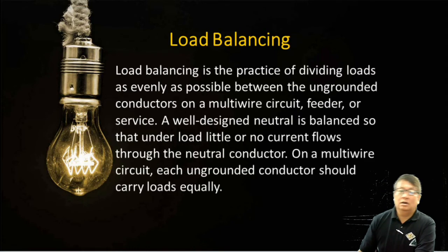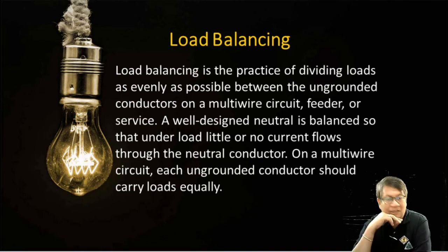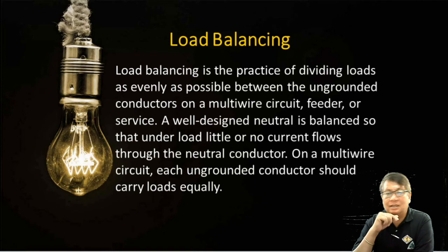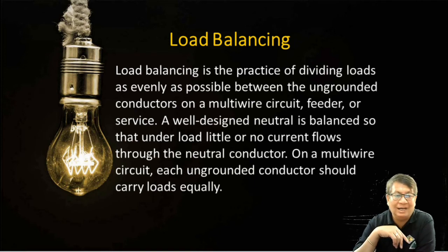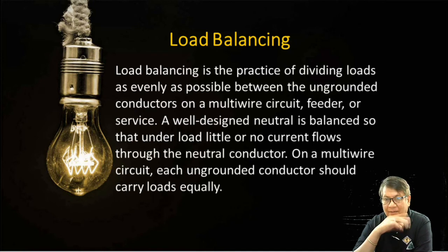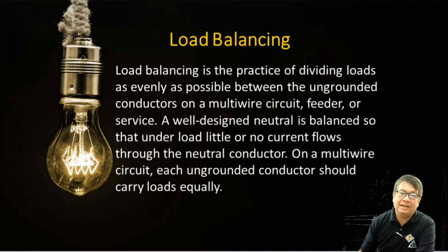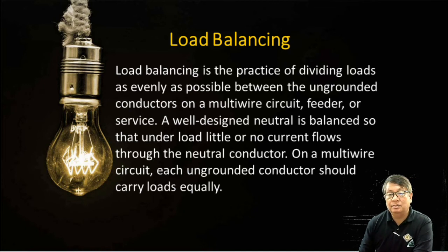Okay? So we have also this load balancing. Ano po ba itong tinatawag natin na load balancing? Load balancing is the practice of dividing loads as evenly as possible between the ungrounded conductors on a multi-wire circuit feeder. Meaning to say that this load balancing is trying to balance our system. Sana mabalance natin yan para walang kuryente na lalabas doon or the neutral path, no? So para hindi tayo ma-electrocute. A well-designed neutral is balanced so that under load little or no current flows through the neutral conductor. On a multi-wire circuit, each ungrounded conductor should carry loads equally.